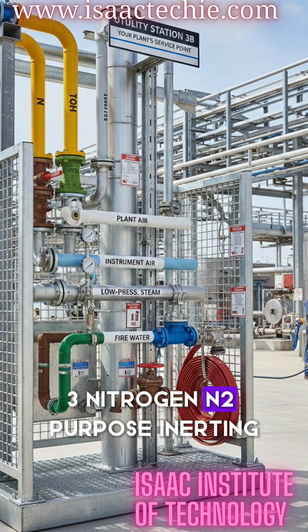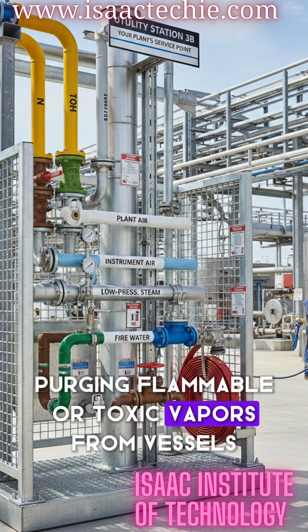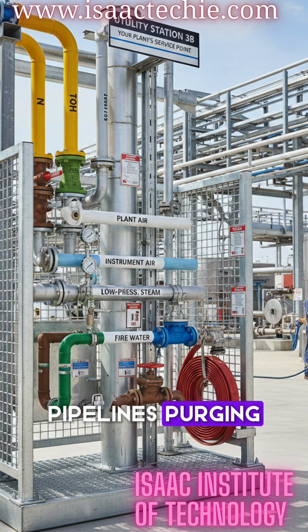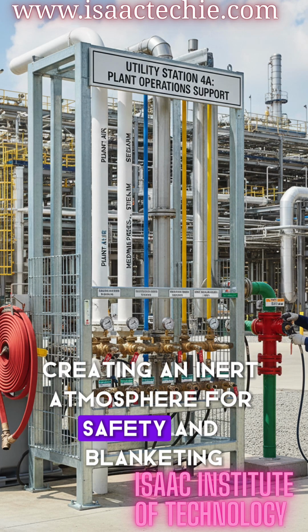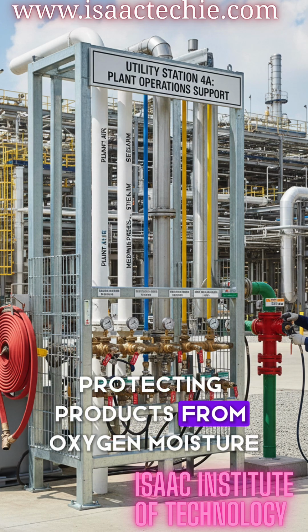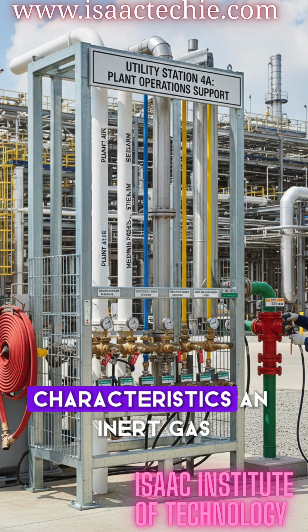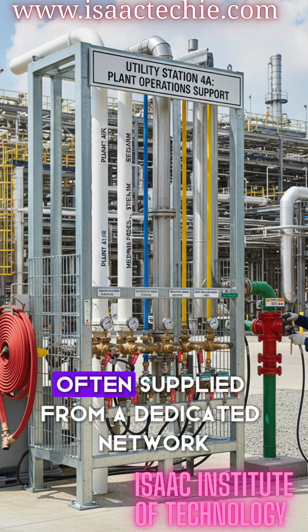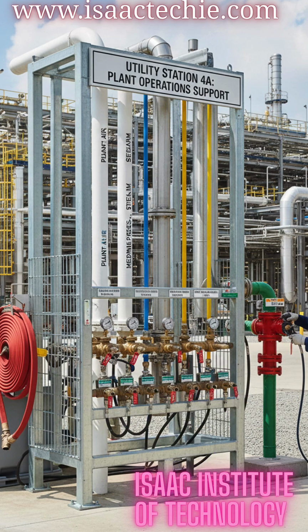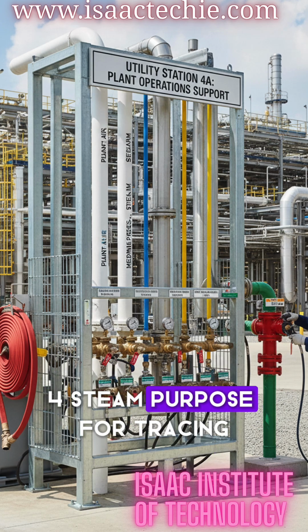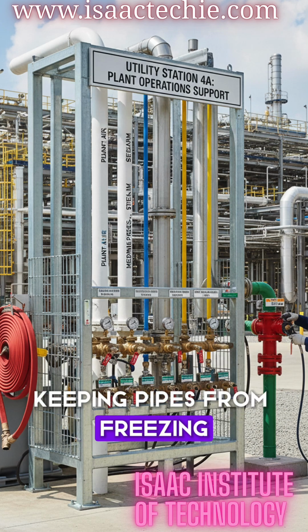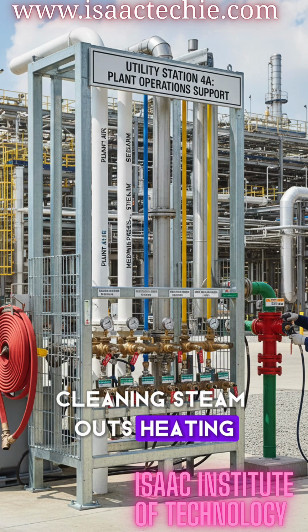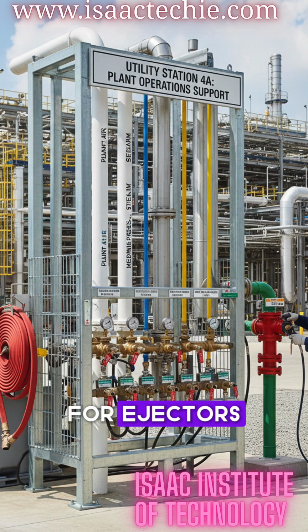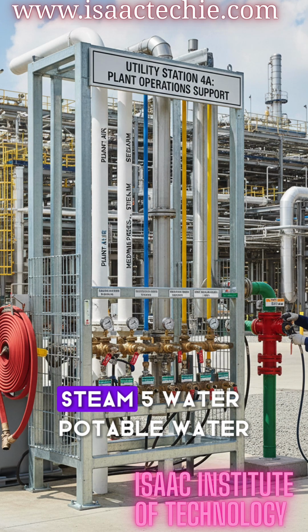3. Nitrogen, N2. Purpose: inerting, purging flammable or toxic vapors from vessels and pipelines. Purging, creating an inert atmosphere for safety, and blanketing, protecting products from oxygen and moisture. Characteristics: an inert gas, often supplied from a dedicated network. 4. Steam. Purpose: for tracing, keeping pipes from freezing, cleaning steamouts, heating, and sometimes as a motive force for ejectors. Characteristics: usually low pressure or medium pressure steam.